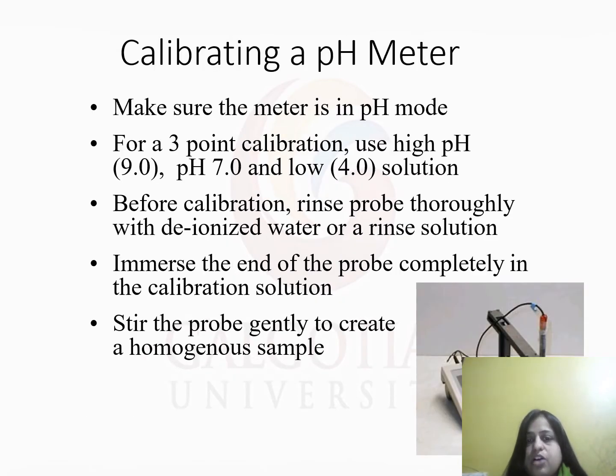So how can we calibrate it? Make sure the meter is in pH mode. For a 3-point calibration, use a high pH 9, pH 7, or low pH, that is pH 4, solution. Before calibration, rinse the probe thoroughly with deionized water or a rinse solution. Immerse the end of the probe completely in the calibration solution. Stir the probe gently to create a homogeneous sample.